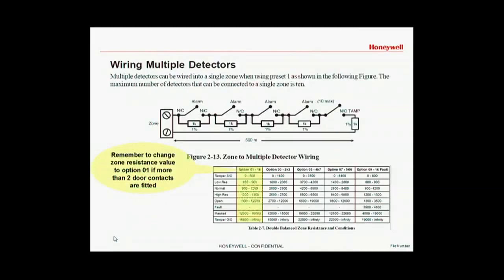If wiring multiple doors on a single zone, we need to change the option to option 01 from the default option 09. This is because if more than two doors were open you would indicate first fault, and then as more doors were opened you'd be in a mask condition. So reprogram the zone input to be 01.